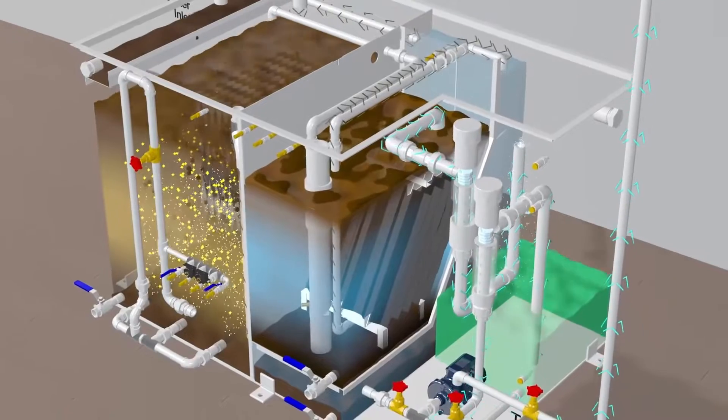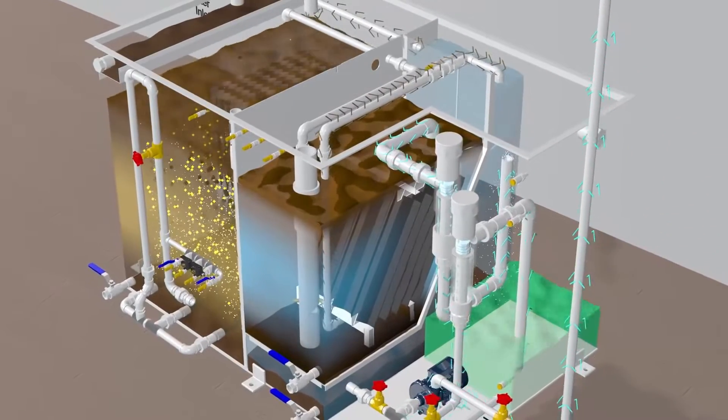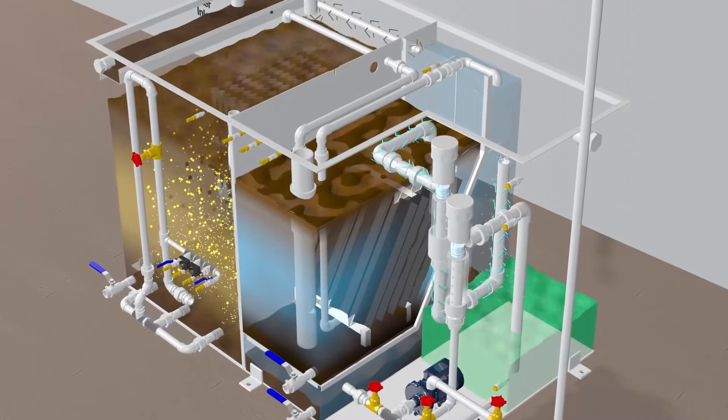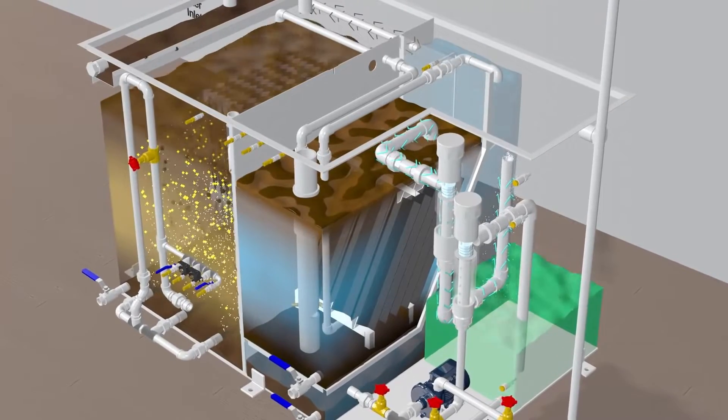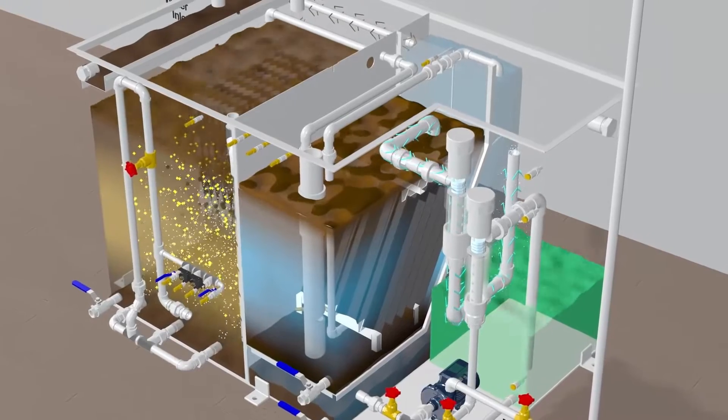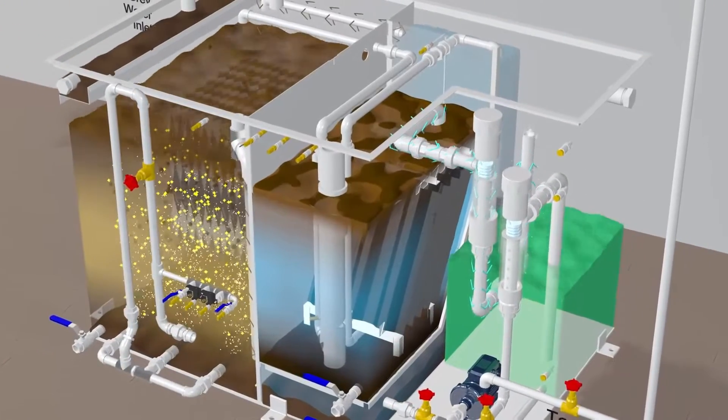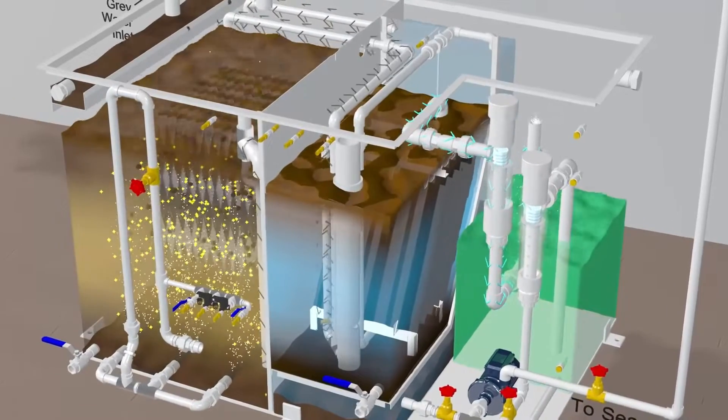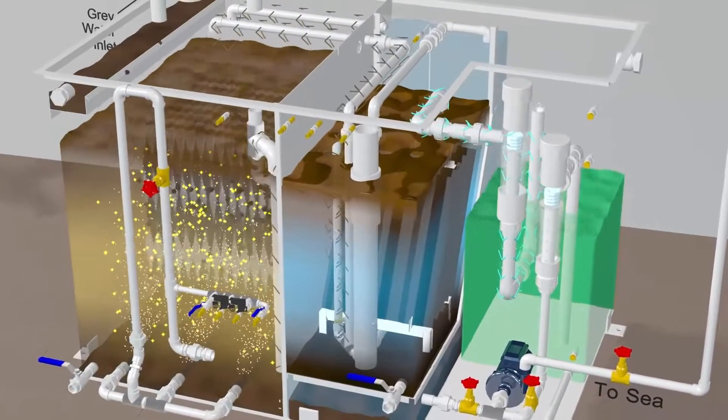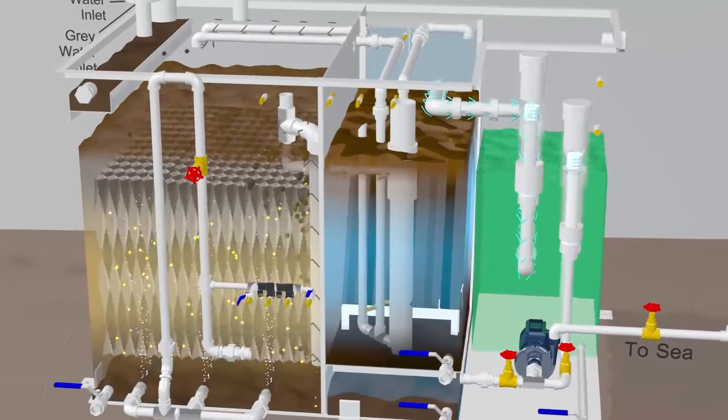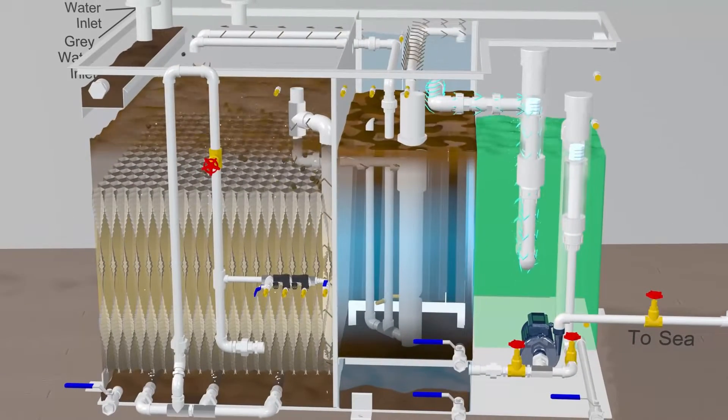Precautions for efficient operation of STP: The aeration blower is installed to run continuously as it helps the microorganisms to sustain and grow. Never switch off the blower as it will cause the death of microorganisms, which will in turn reduce its clarification efficiency and take days to grow microorganisms again.